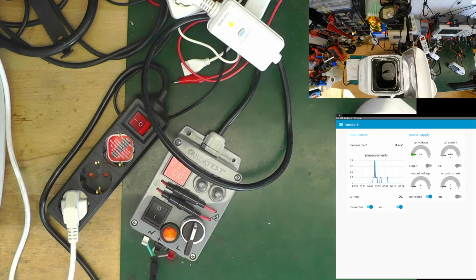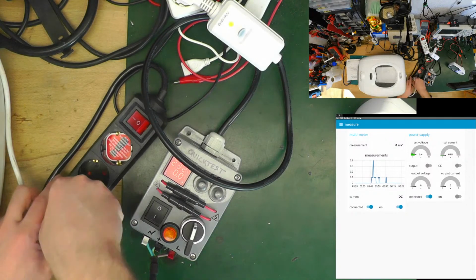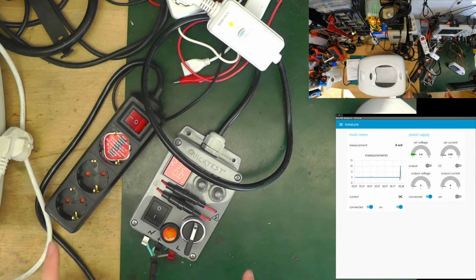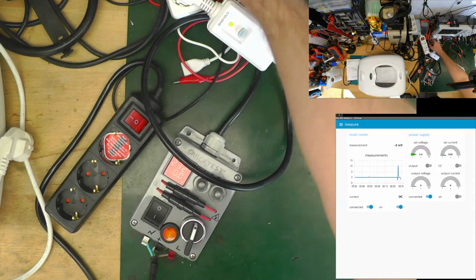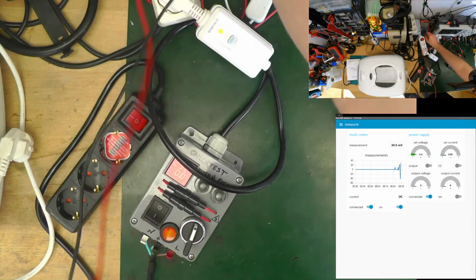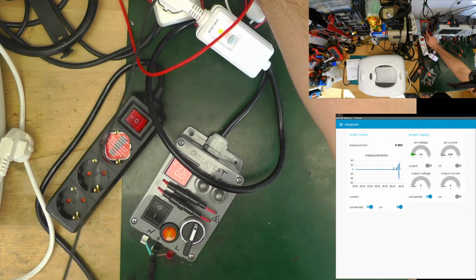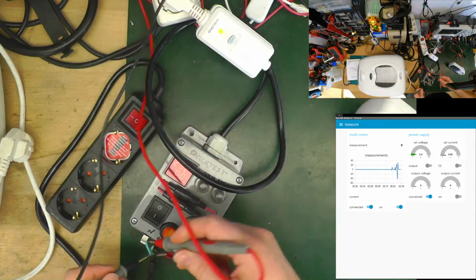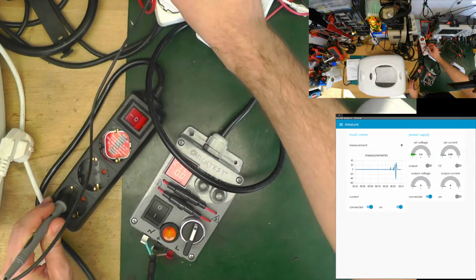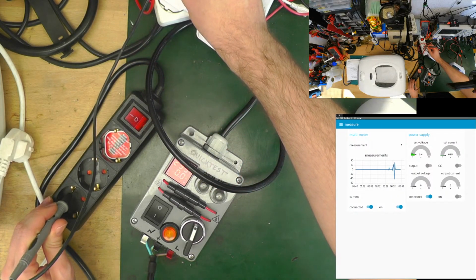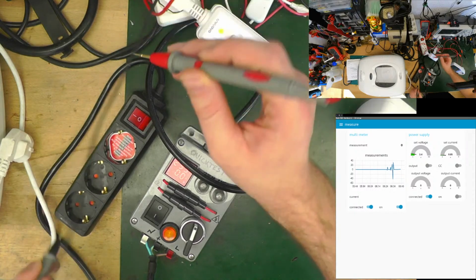Let's switch it off and try if actually earth is really connected to earth, because this thing should trip. So, continuity test. This earth is connected to this one. Yes, so earth is going through, so at least this is secure.